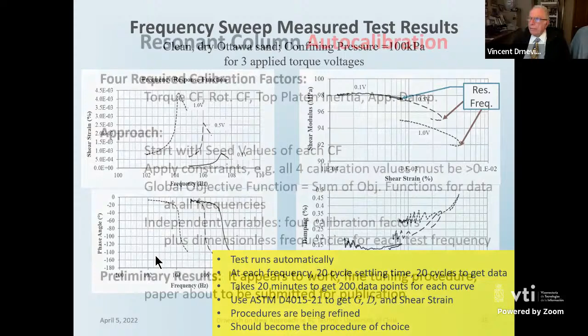The other thing that happens in a conventional resonant column test is that it takes a certain amount of time to adjust the frequency to get resonance. And finally, when you do, you have to take the measurements. You really have no ability to determine how many cycles of strain have been applied to that specimen. You can approximate it by taking the frequency and multiplying by the time that you were fiddling around getting the resonance. But in this case, you can set that. And so it's very easy to determine how many cycles you apply to the specimen in order to get the values of strain.